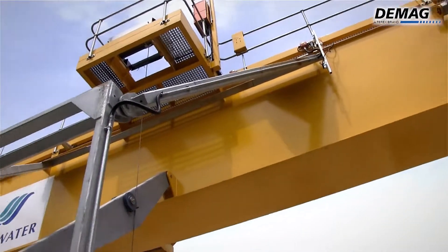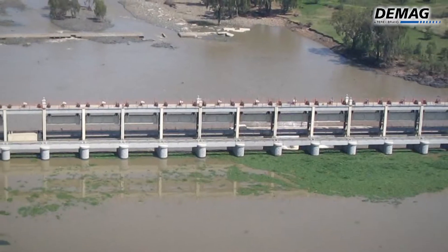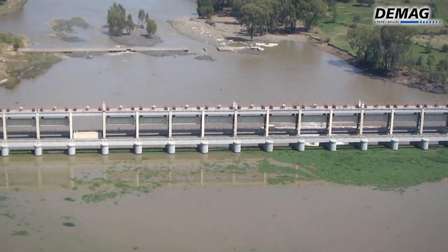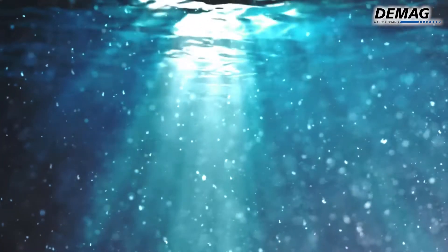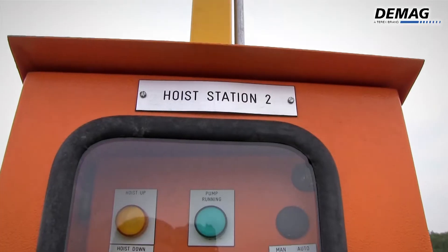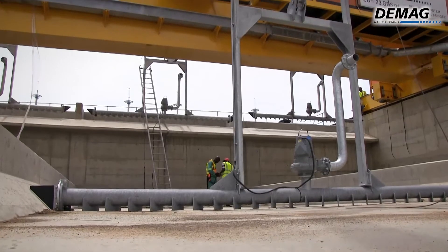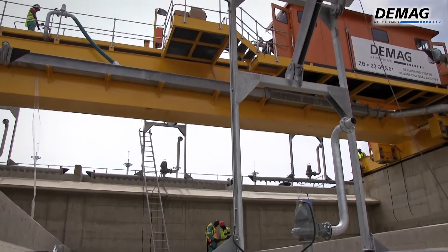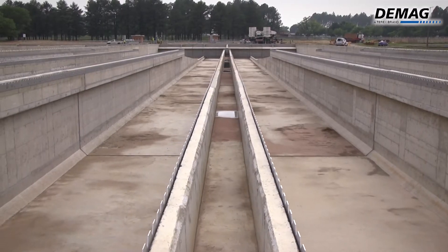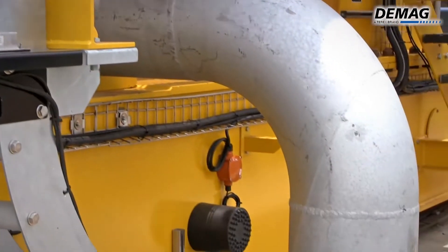Demag's machinery will form an integral part of the process of converting water from the Val Dam and River into potable water, as flocculators mix incoming water with flocculants that attract suspended solids and result in sludge that settles at the bottom of the tank. This automated desludging bridge will scour the 10,000 square meter floor to remove this sludge layer. In total, 200 million litres of water is expected to flow through the system's tanks and 16 million litres of sludge pumped out by the bridges each day.